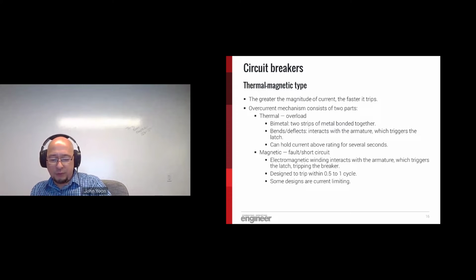The magnetic portion of the breaker works on the principle of electromagnetic fields created by the flow of current, the right-hand rule. The magnitude of the field is proportionate to the magnitude of current. Through design of the breaker, you can create a magnetic field that will force a switching armature open. More current means greater magnetic field, which will open the contacts much faster. When subjected to full fault current, the typical circuit breaker will open in a half to one cycle. When we look at time current curves a bit later, this will become a little bit more apparent.